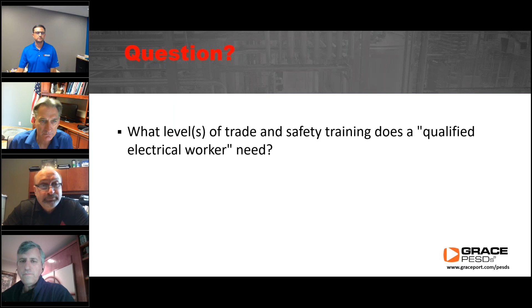Not day one, but eventually you're going to get this 1st year apprentice. He's going to work with you. You're going to show him how to do energized work. So that's the other challenge, the arc flash and shock training content. It will most likely not be adequate in the trade qualification training for apprentices and other task qualified workers. So in my opinion, it does have to be provided separately by the employer when that worker arrives on site. They should provide extra or separate arc flash and shock training to NFPA 70E and Z462, because the training in the institution will not be adequate.